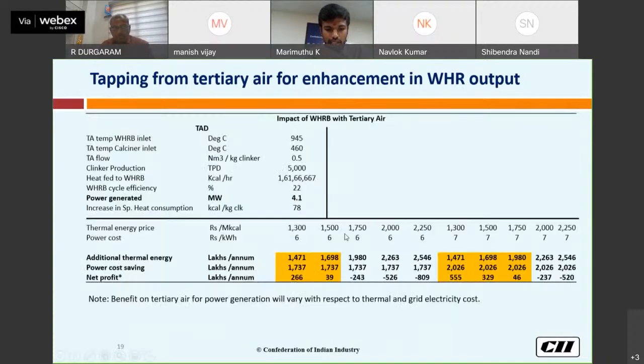So this is the calculation which gives the payback period, the improvement in power generation, as well as savings. With a drop of 945 to 460 degrees, for the 5000 ton production we will get power generation of around 4.1 megawatt. But the thing is, we need to add more heat input to the calciner because we are extracting heat from the tertiary air to the boiler, so it will increase the specific heat consumption. The savings calculation is presented there.